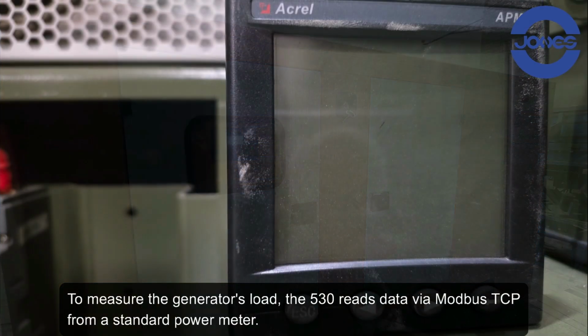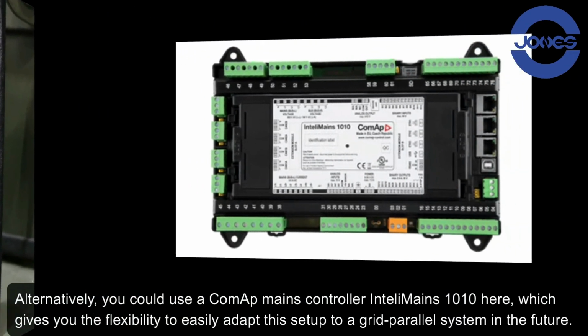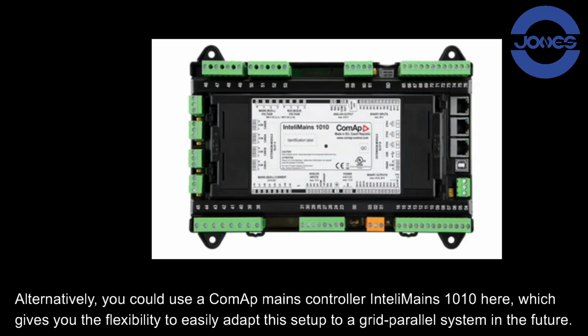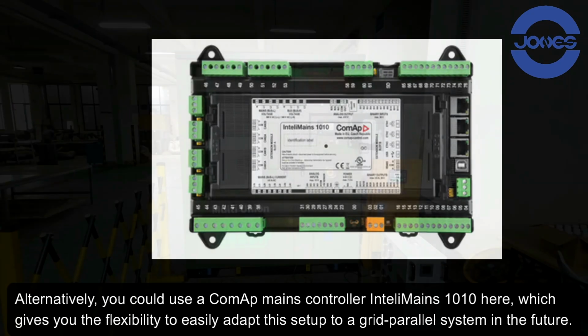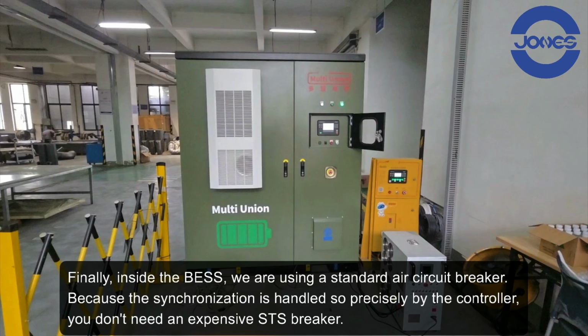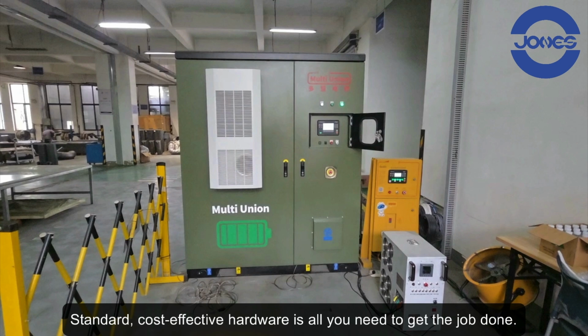To measure the generator's load, the 530 reads data via Modbus TCP from a standard power meter. Alternatively, you could use ComAp's mains controller here. This would give you the flexibility to easily adapt the system to a grid parallel system in the future. Finally, inside the BESS, we are using a standard air circuit breaker. Because the synchronization is handled so precisely by the controller, you don't need an expensive STS breaker. Standard cost-effective hardware is all you need to get the job done.